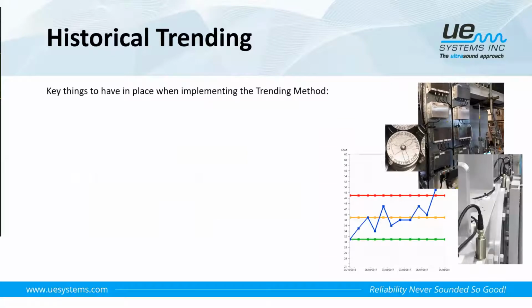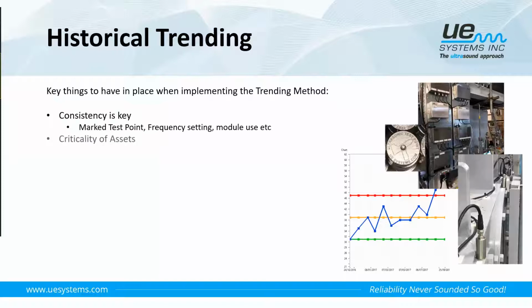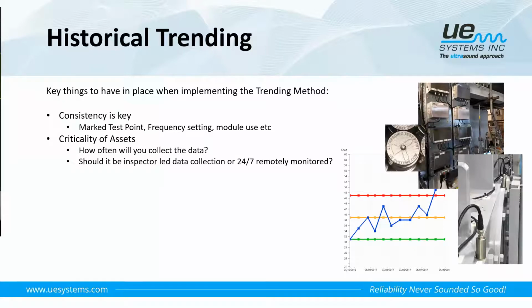So there are some key things to have in place when implementing the trending method, the historical trending method. Consistency is key. Having marked test points, making sure that the frequency setting is the same every time, making sure that we use the same modules each time. Have we performed a criticality analysis study of all of our assets on site so we understand how often we will want to collect our data, and maybe if they are critical enough, do we want to be using 24/7 remotely monitored equipment to help keep track of the condition of our highly critical assets? It's an important thing to consider.